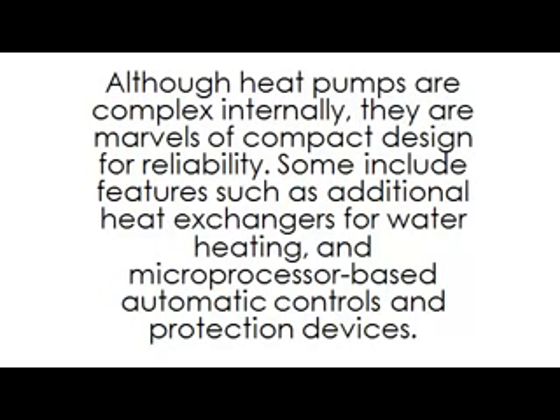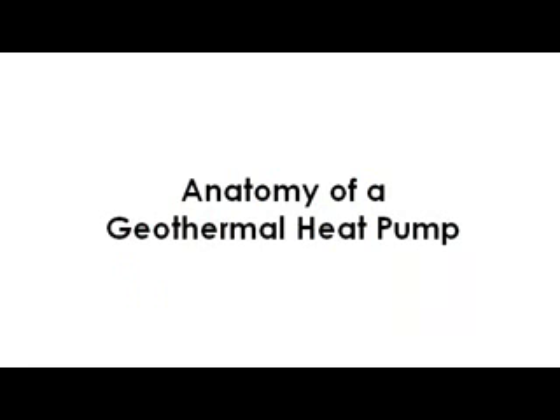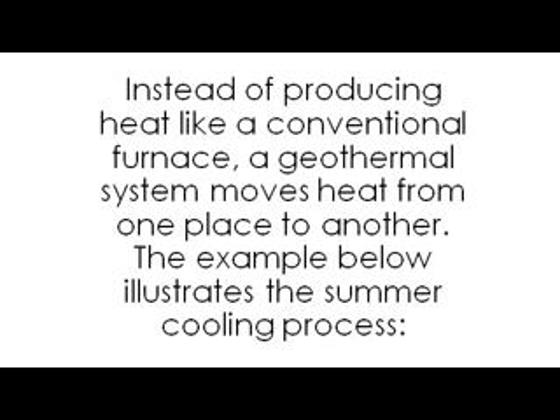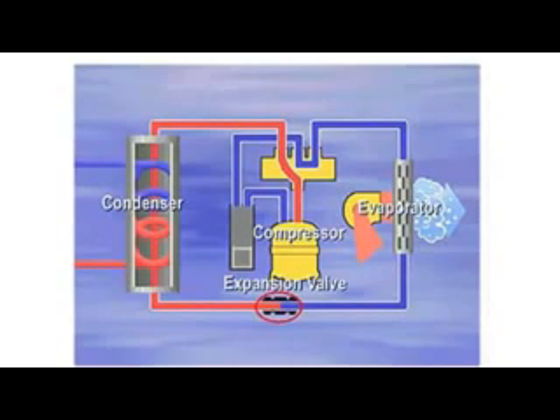Although heat pumps are complex internally, they are marvels of compact design for reliability. Some include features such as additional heat exchangers for water heating and microprocessor-based automatic controls and protection devices. Anatomy of a geothermal heat pump. Instead of producing heat like a conventional furnace, a geothermal system moves heat from one place to another. The example below illustrates the summer cooling process. The cool, liquid refrigerant enters the indoor coil during cooling. As it enters the coil, the temperature of the refrigerant is between 40 and 50 degrees. As warm, moist room air passes over the cool coil, the refrigerant inside absorbs the heat. The new, cooler, drier air is circulated back into the room with a blower fan.